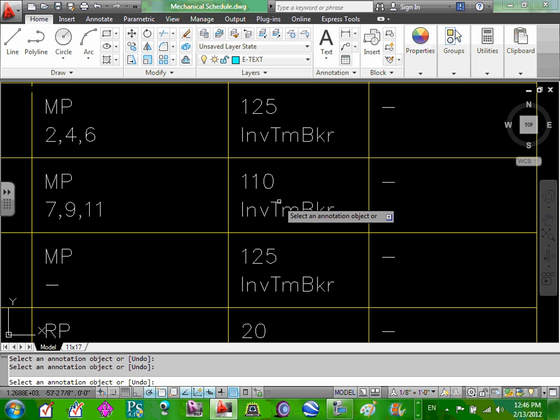You're absolutely right. Almost always we match the overcurrent protection device to the cable, except if you're feeding mechanical equipment, motors, HVAC equipment, chillers, heaters, for example. In a heater, you almost match the overcurrent protection device, 1.25, 1.25. But mechanical equipment that has a machine in it, motors, don't, because of the inrush. Any questions about this? Yes, sir.